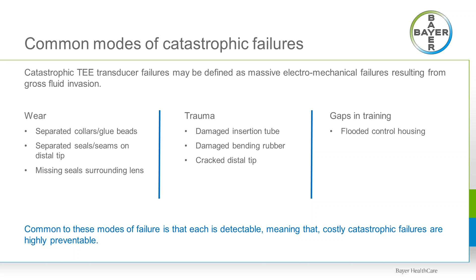All right, so it's possible to classify the common sources of catastrophic failures into three groups. Some of those are attributed to normal wear, some of those are attributed to trauma, and some of those can be attributed to either gaps in training or gaps in a process somewhere. Visual inspections, leakage testing, and preventive maintenance really provide the ability to detect these failures. And really what I'm trying to say is costly, catastrophic failures are highly, if not fully, preventable. So, unfortunately, most TEE probes are kept in service until a major failure occurs.